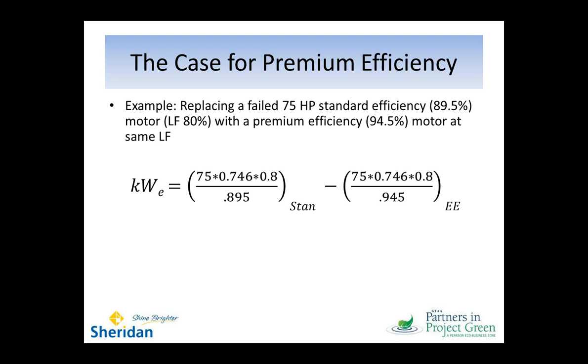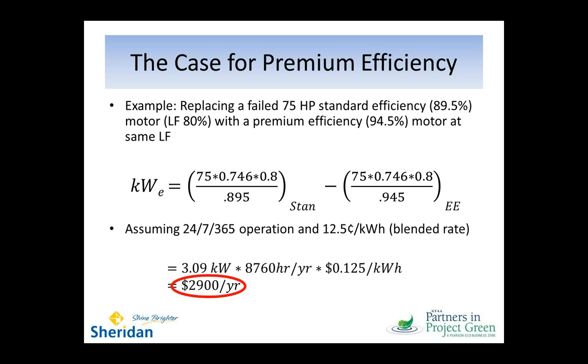And you can see from the calculations in the brackets that all that I've really changed, one to the other, is the efficiency in the denominator. And the equation shows that we should have a net savings of about 3.09 kilowatts, and that's continuous. If I multiply that times the hours of operation per year, in this case it's a 24/7, 365 operation, and you multiply it by your cost per kilowatt hour, in this case we chose 12.5 cents because that's fairly typical for Ontario and in this area, that yields savings of $2,900 a year just on making the switch to a higher efficiency motor.